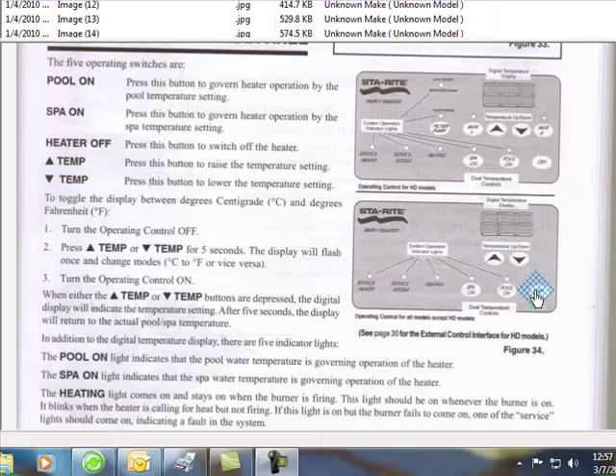But this is how you change it from Celsius to Fahrenheit. Turn off the equipment. Leave the power on. Hit the TEMP button, either up or down and hold it. And it'll flash. Turn on the pool equipment.